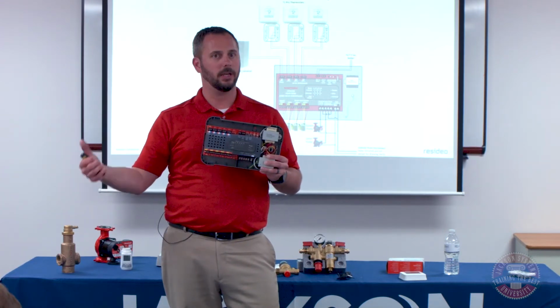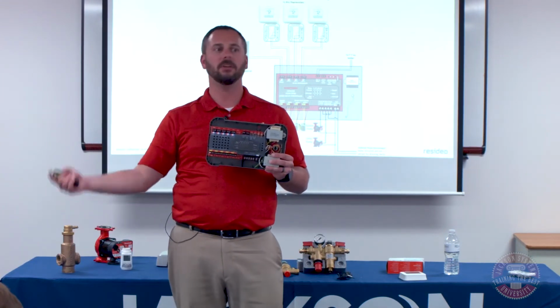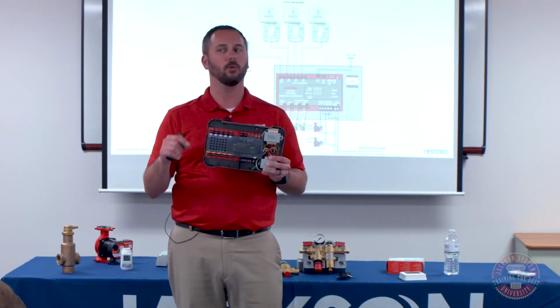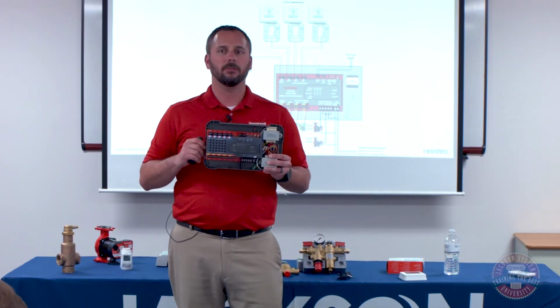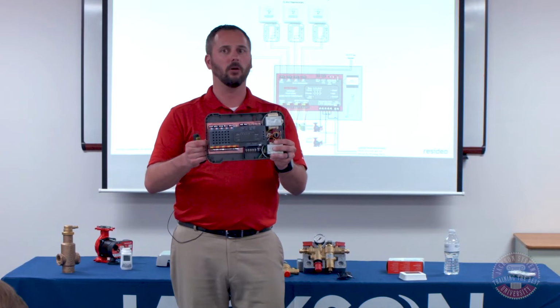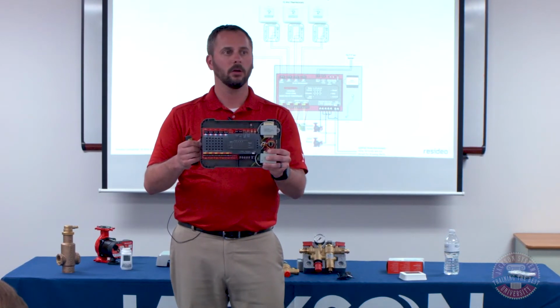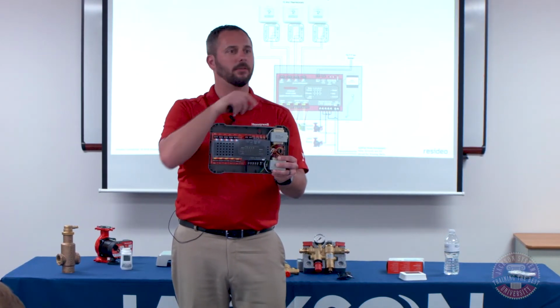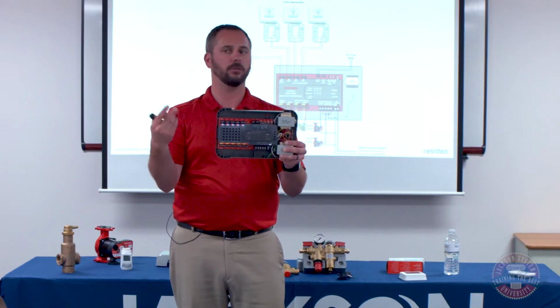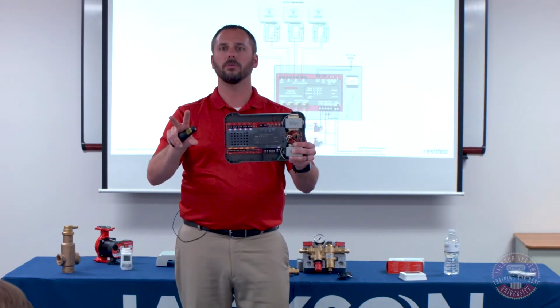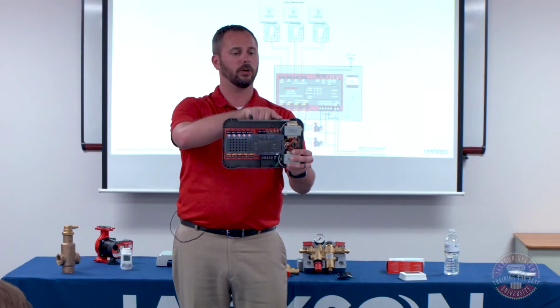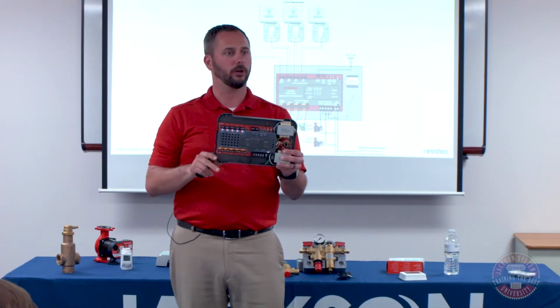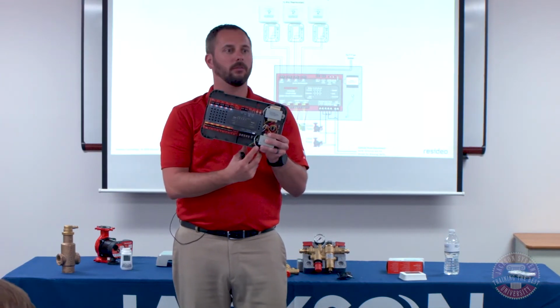So you're going to have your indirect wired into the boiler, you're going to have your space heating and boiler pump all wired into the boiler. With that being the case, literally all this is a zone valve relay or a pump relay, so you can just give calls for heat indefinitely. So you can put 2 boards side by side, so if it's a 10-zone system, you can put 2 5s side by side and take the boiler in switch off of each one right back to the boiler, because you're not using the high voltage relays.